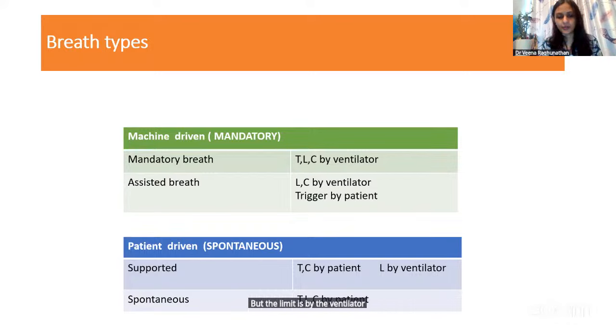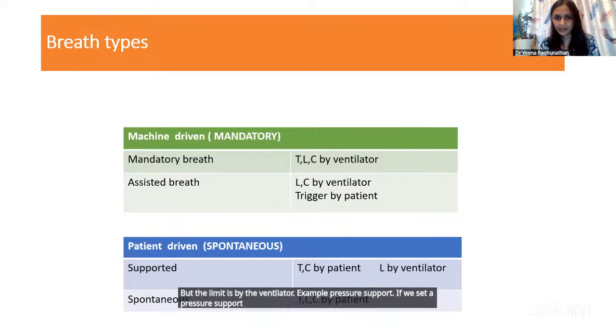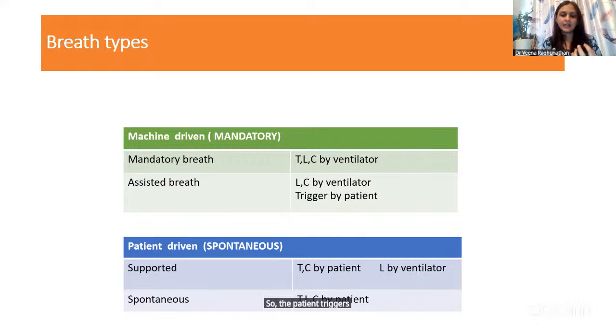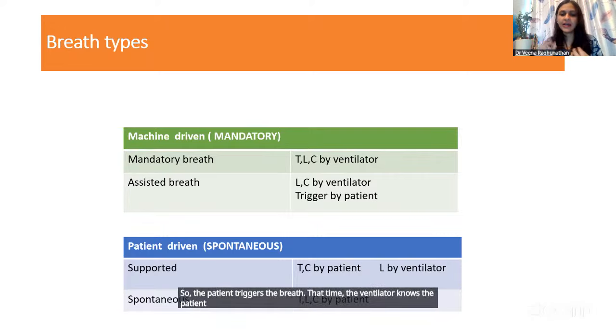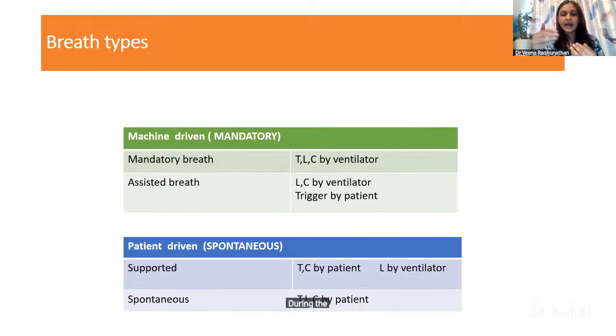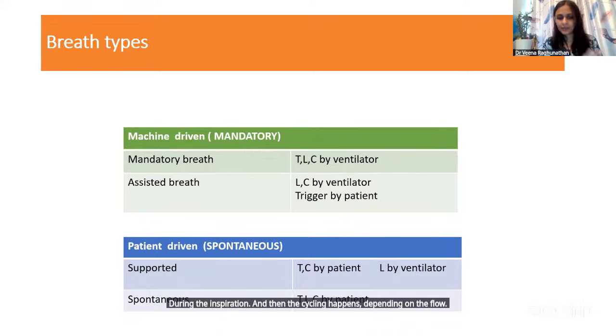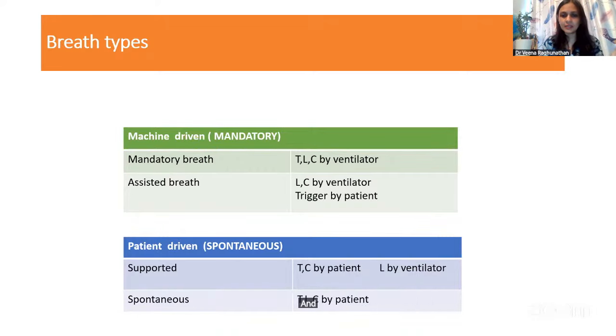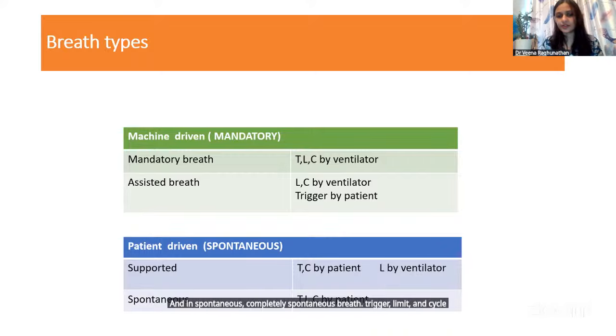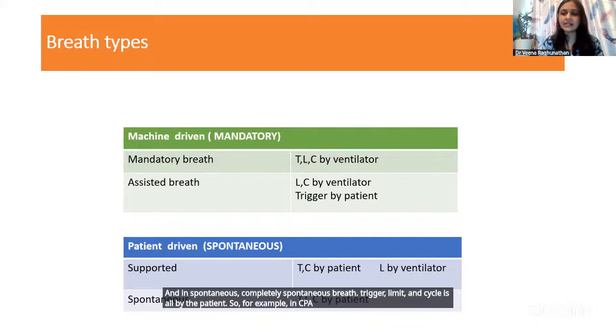Example, pressure support. If we set a pressure support of 10, the patient triggers the breath, at that time the ventilator knows the patient has triggered, and it gives a pressure of 10, which is the limit during the inspiration. And then the cycling happens depending on the flow of the patient. So cycling and trigger are by the patient, but the limit is by the ventilator. And in a completely spontaneous breath, trigger, limit, and cycle are all by the patient. For example, CPAP mode is an example of a totally spontaneous mode.